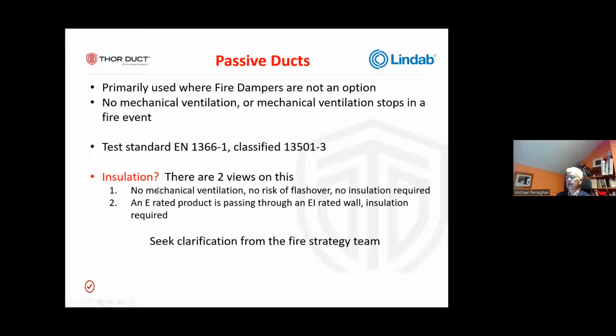It doesn't make sense. The other one is that it's an E-rated product because products are rated E for integrity, I for insulation. So it's an E-rated product which is passing through a wall that is rated EI. So the I requirement needs to be maintained, therefore insulation is required.